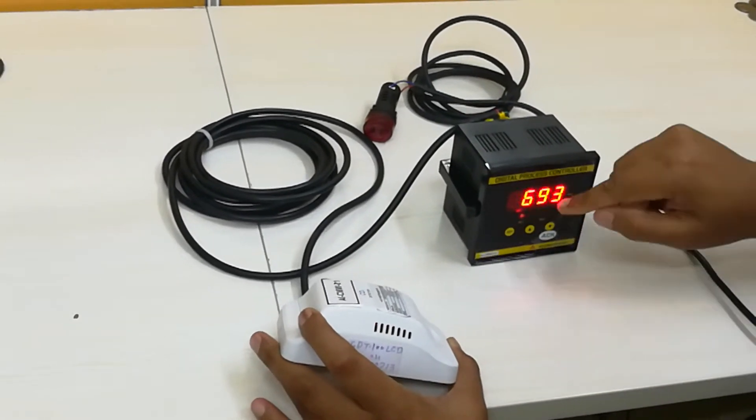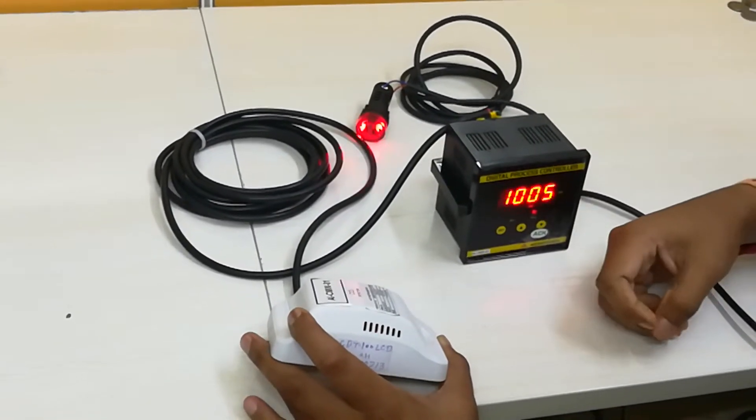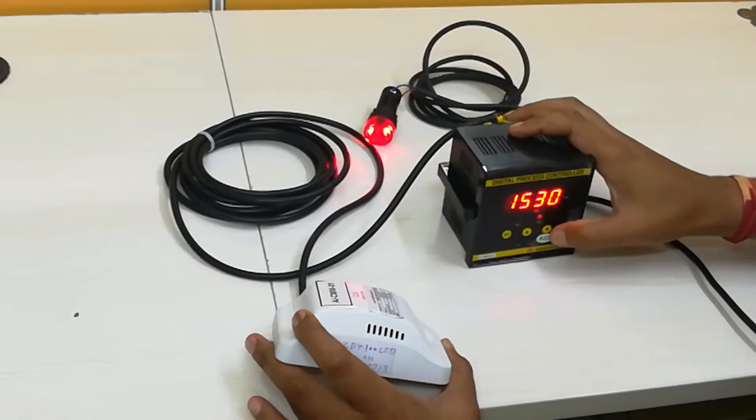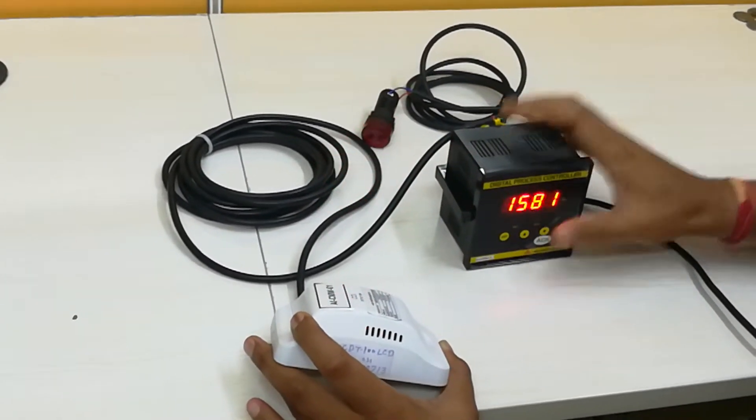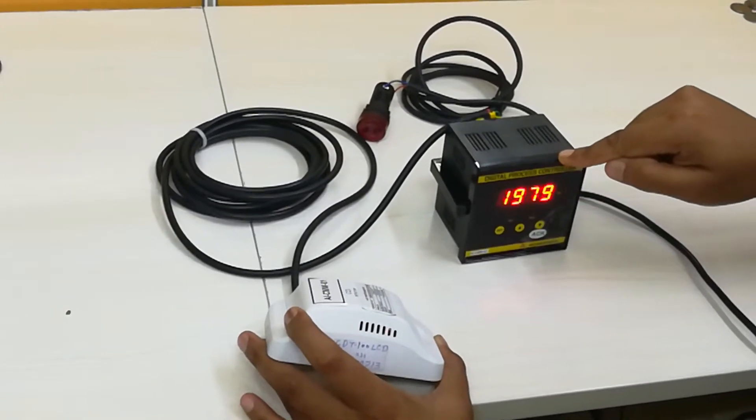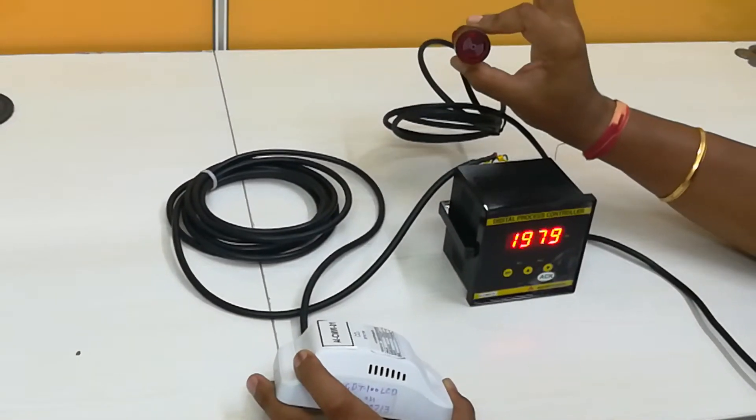It is currently set to 900 ppm. Now we can see that it has crossed. We will just press the acknowledgement key. We have seen that when it crossed 900 ppm it automatically triggered this audio visual buzzer.